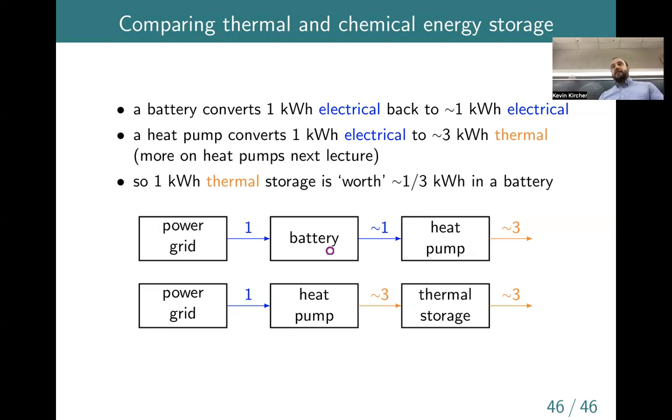And then there's deliberate dissipation, or deliberate discharging. So if we think of the building fabric, the deep thermal mass as an example, we charge it by raising the temperature in this room a couple of degrees, that warms up the mass relative to what it would have been in baseline operations. So to discharge it, we could lower the temperature in the room back to the set point, or maybe even by a couple degrees below that. So now maybe the thermal mass is at 74 Fahrenheit because we held the room at 74 for a long time, but we drop the air to 70, say.